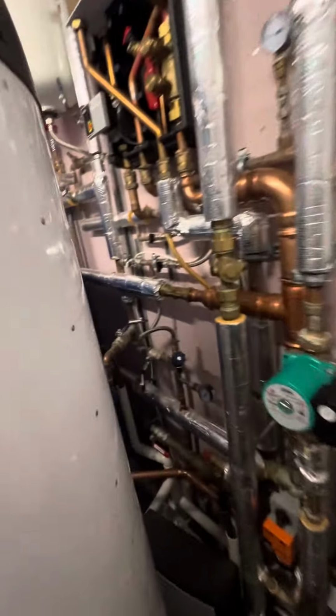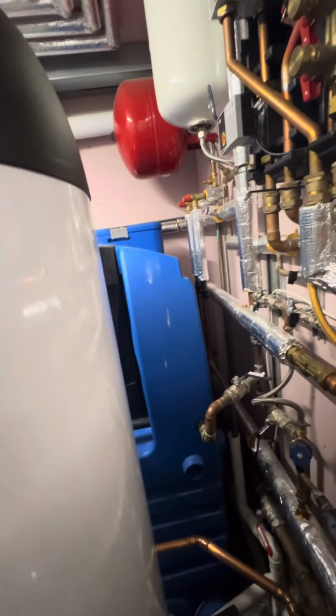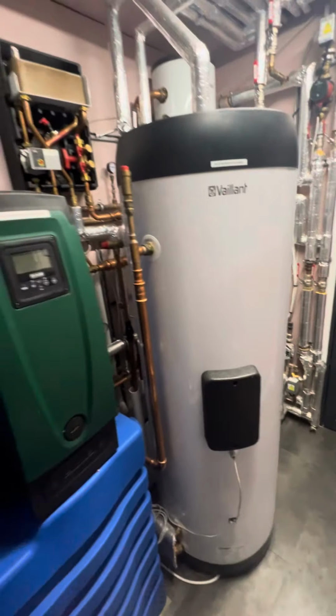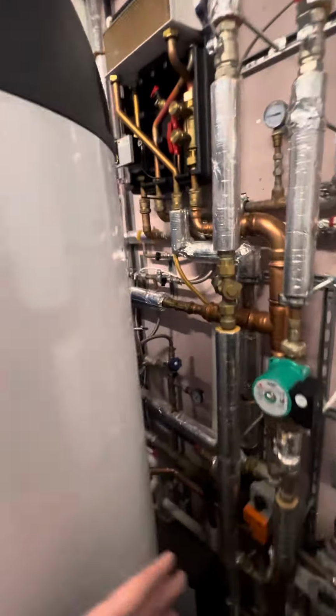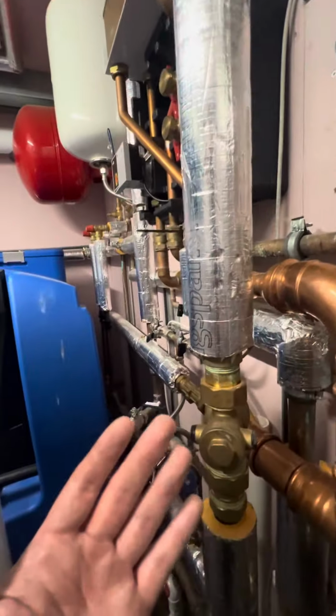So here we have 4 pipes. We have 2 flows, 2 returns, 1 for each heat pump. So one of these heat pumps can do heating and hot water, the other can just do heating. The reason only one can do hot water is because it's only a 300 litre cylinder and we'll never need 2 heat pumps to heat this. But the heat pump that does hot water can also come on to boost the central heating if required.